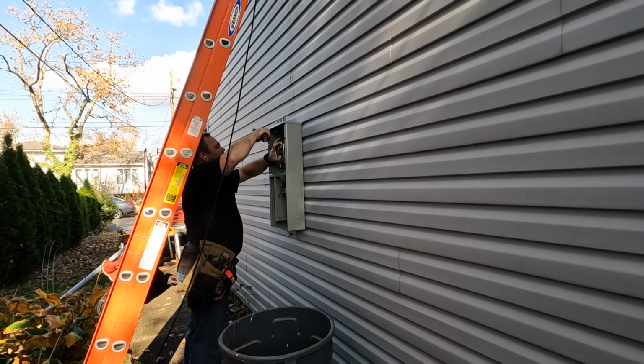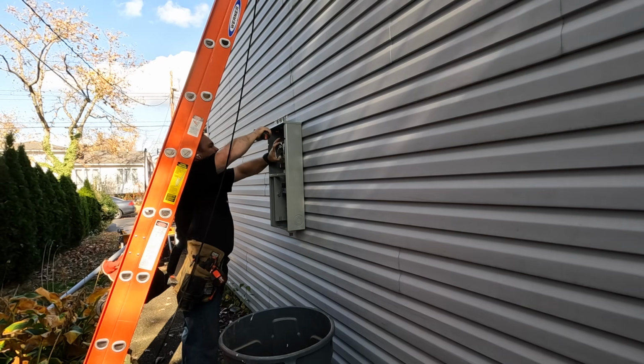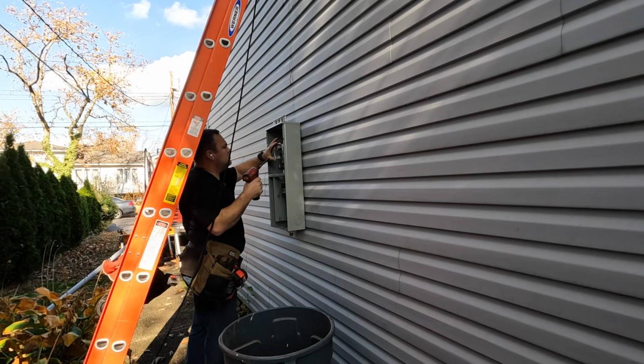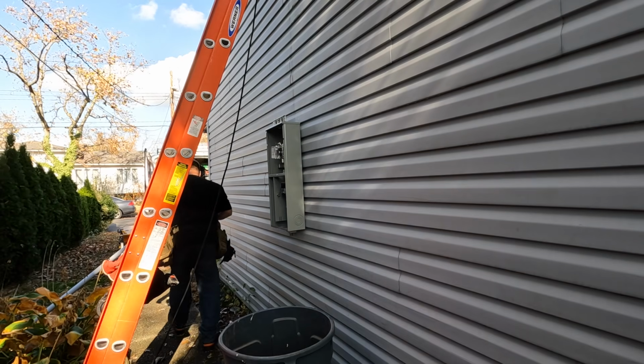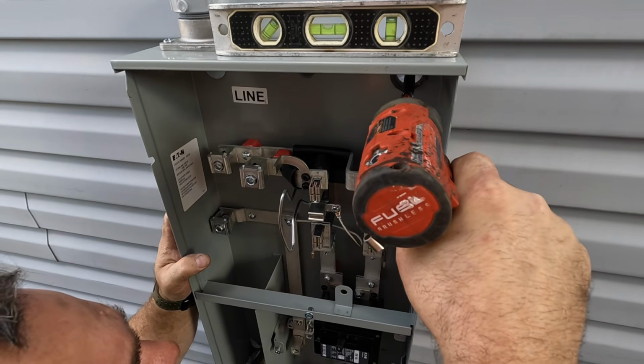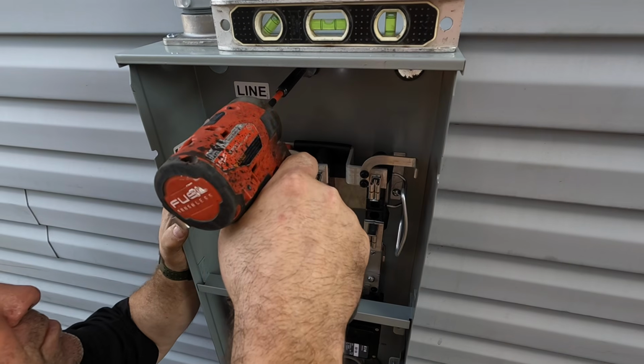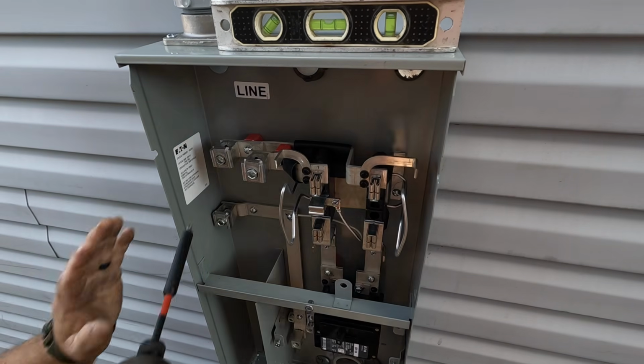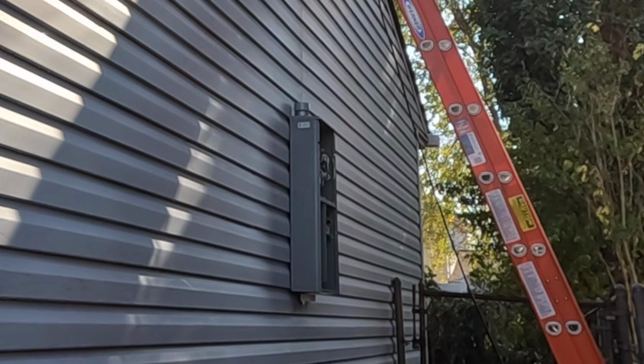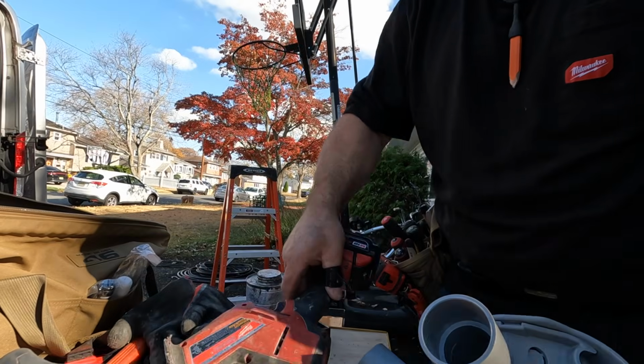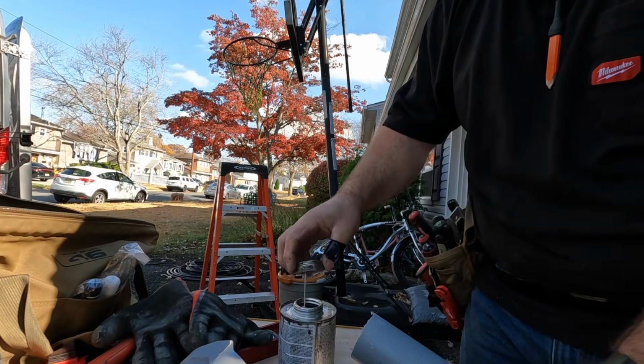I'm just going to install a screw here just to keep it in place, and then I'll come back and wedge the duct seal behind the finished washer. Now here you've got to be careful, because on the other side of this enclosure is the electrical panel. So we want to make sure we don't come through the panel on the inside.